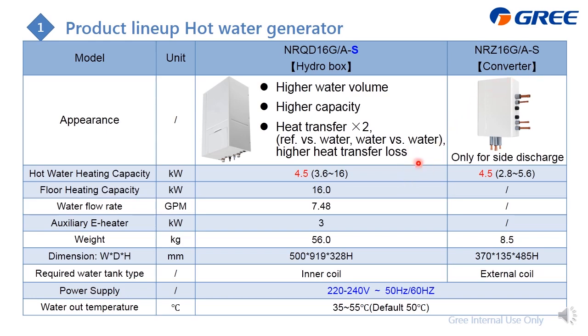And so of course the heat transfer efficiency for the converter is a little bit higher. And just because of this, if this connects to the water tank, it must use the inner coil for the water tank. For the converter it must use the external coil. And this is only for side discharge. And this one, inside there is a water pump, and here is the flow rate, and also there is a built-in e-heater of 3 kilowatt. And the maximum water outlet temperature for both of these is up to 55 degrees.